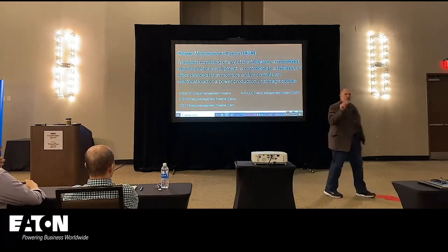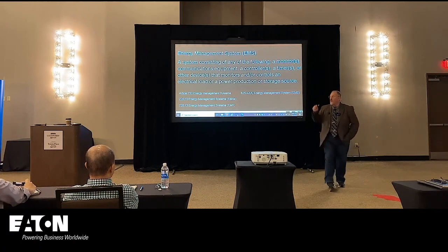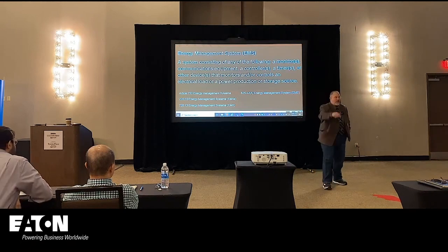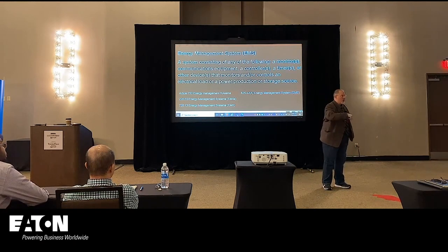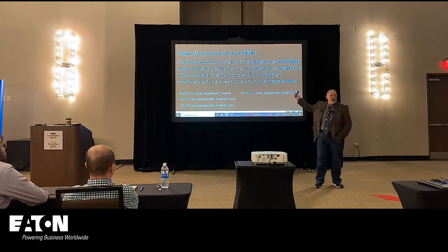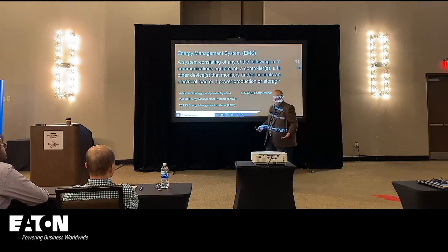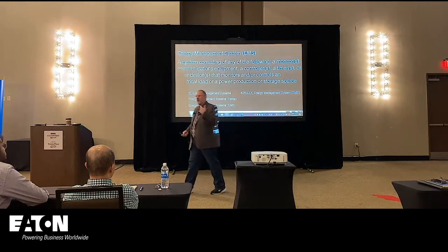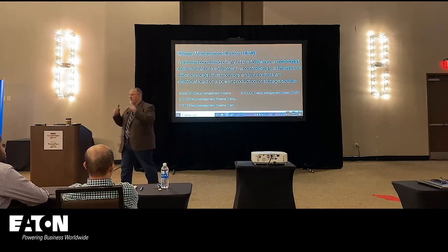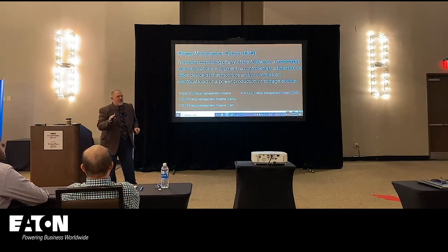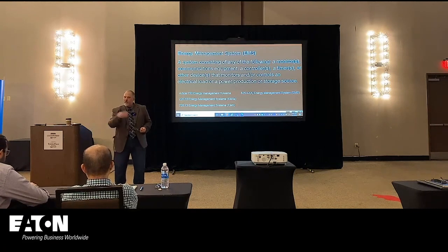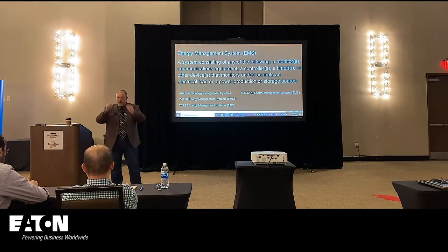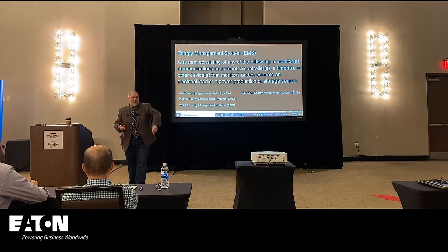And how we leverage the energy management systems in the NEC is we'll tell you, you can size feeders, you can size your service based upon what these energy management systems limit your energy usage to via load control. An important aspect of this is in Article 705 for interconnected systems. The challenge in a 705 system, if I have photovoltaics and I'm coming into a panel board on the load side of the service overcurrent device, not on the line side, but on the load side, I'm going to connect it through a breaker, which hopefully will be reverse power fed capable, right?